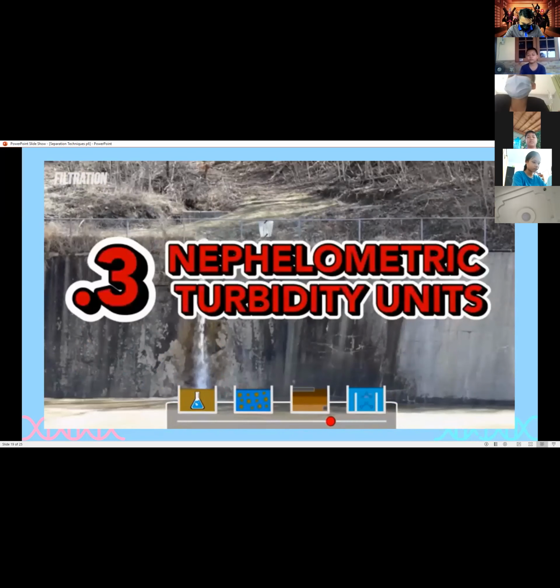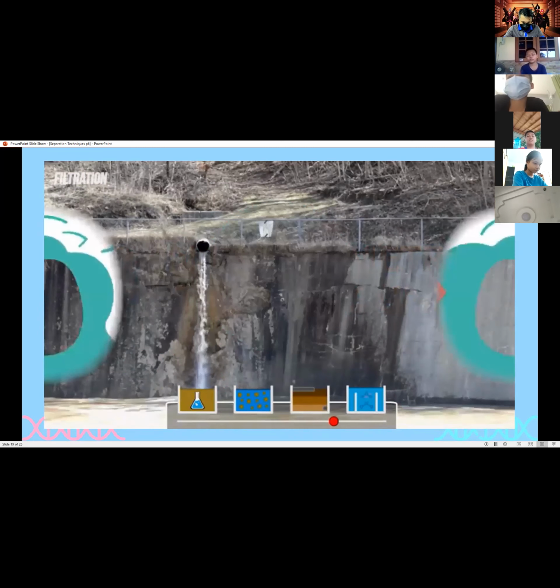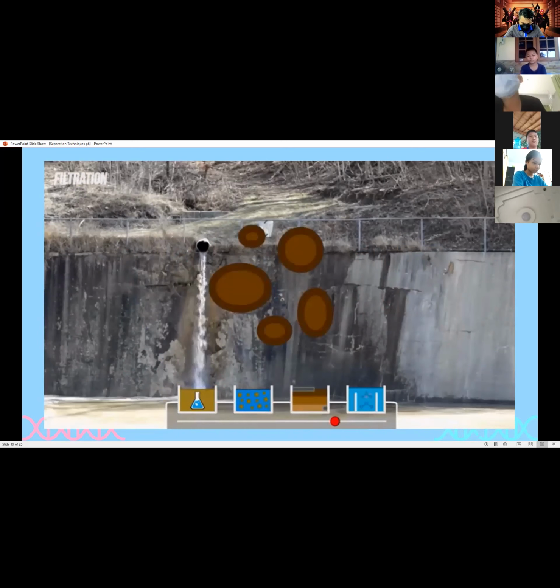However, while not highly technical, sand filters are highly efficient. Water flowing out of sand filters will need to have a clarity of less than 0.3 nephelometric turbidity units, or NTU. Try saying that 3 times fast. Or whatever local code is used for water clarity. This measurement is essentially just a way to determine the number of particles still remaining in the water, or turbidity.